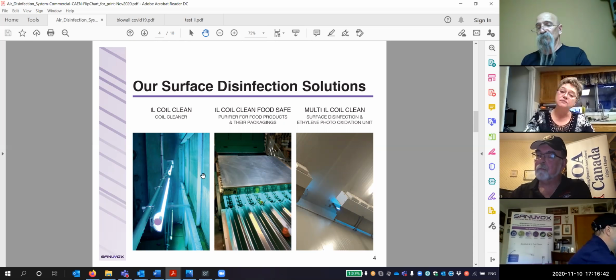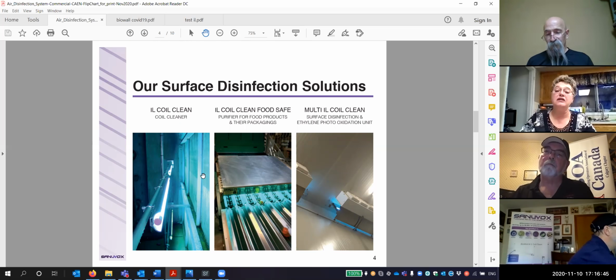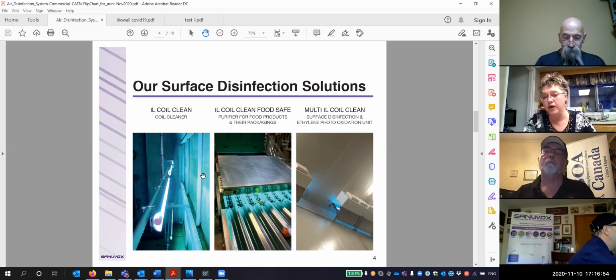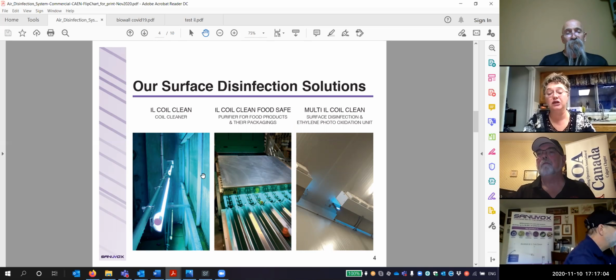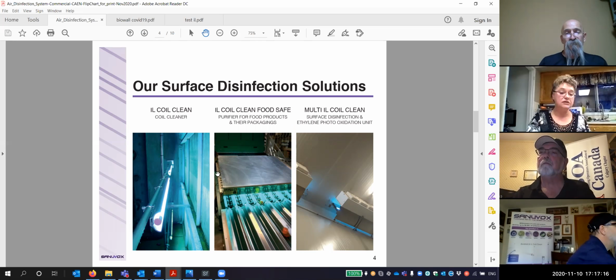And the last big bonus is it is a huge preventative of formicary corrosion from ever developing. What happens is when you get that bacterial biofilm on your coils, the water starts pooling and it turns acidic and starts pitting your copper tubes. And that becomes an equipment failure and is called formicary corrosion. So if you have clean fins, you don't have that situation from ever developing. So these are quite important things that would be a benefit.